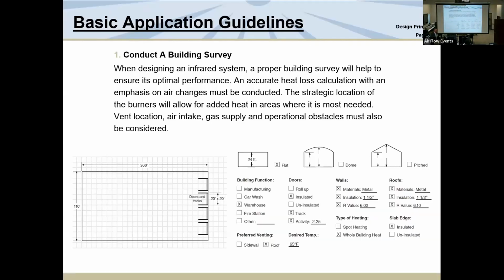What do we do when we need to design with infrared? We need to conduct a building survey, right? And that covers our values of the roof, insulation, floor, is it insulated, the whole use of the building. And I chuckle all the time because people spend so much time on whether the doors are insulated, what the R value of the roof is, is it a 28 or a 30, what the walls are. But nobody ever knows how many air changes are in a building.